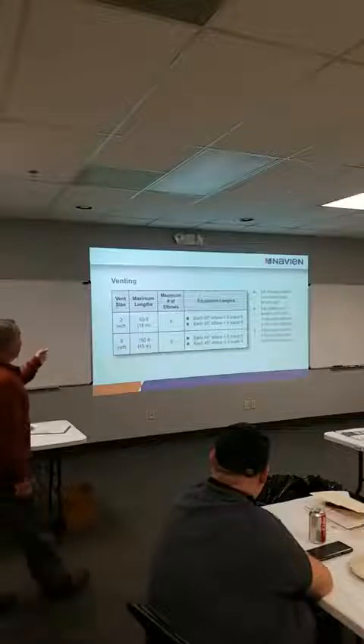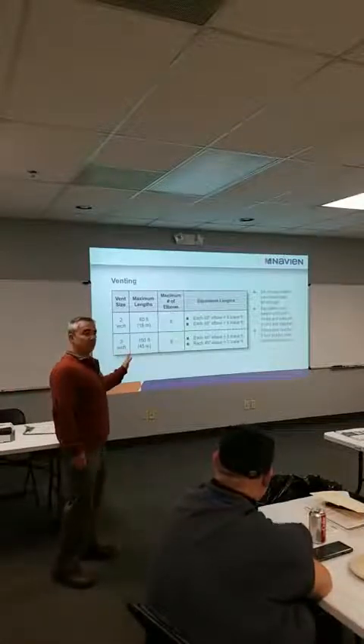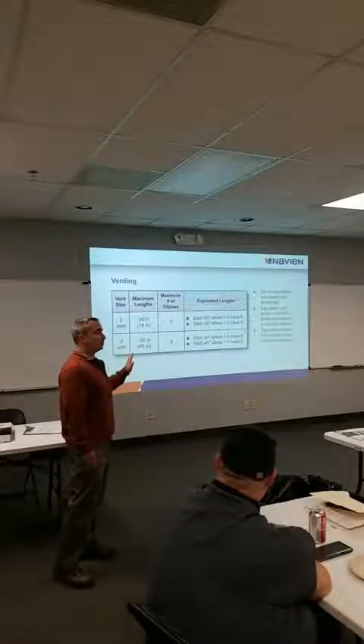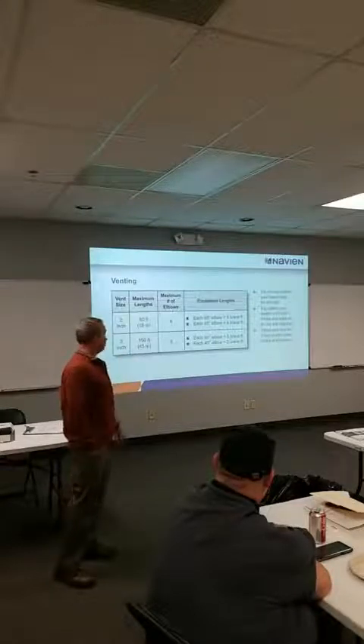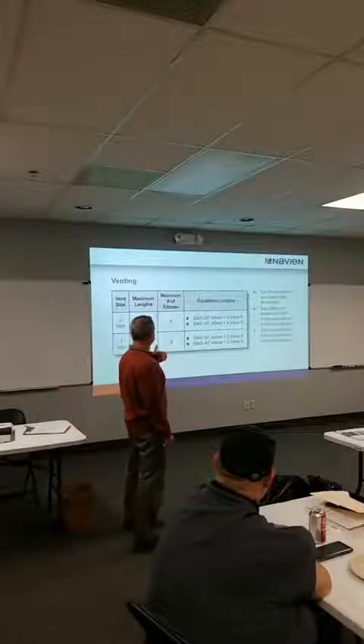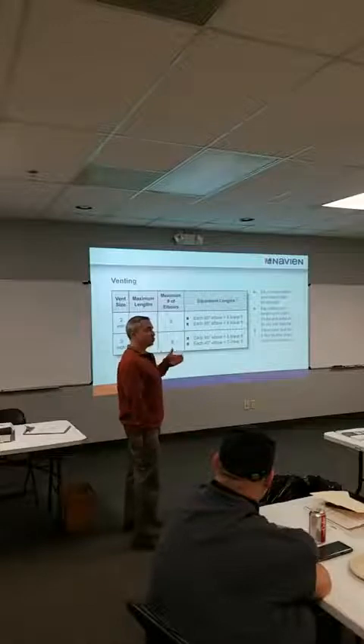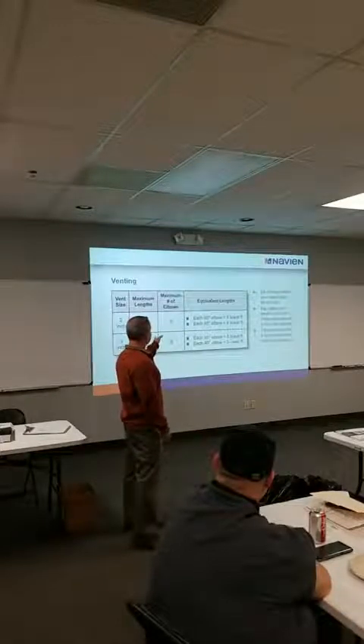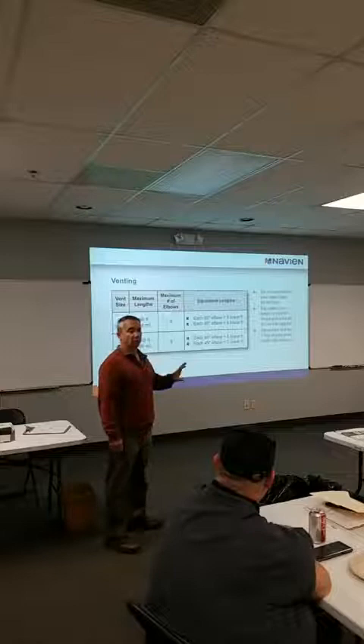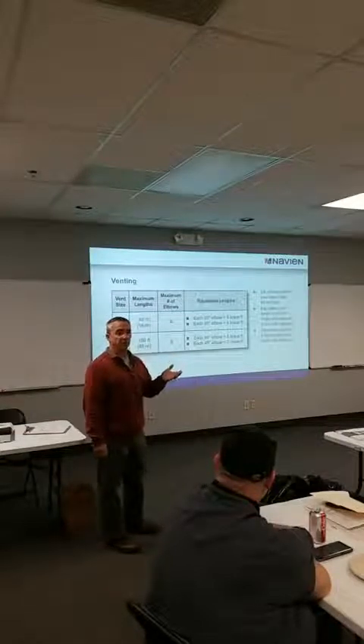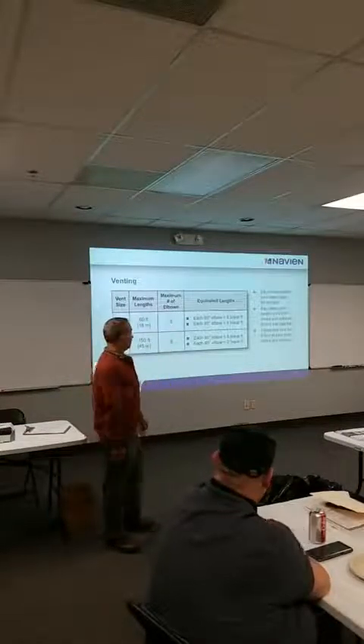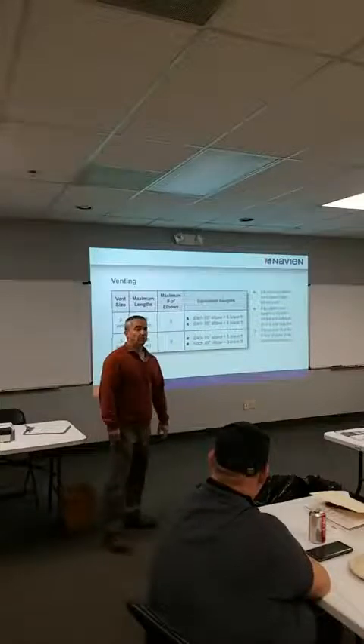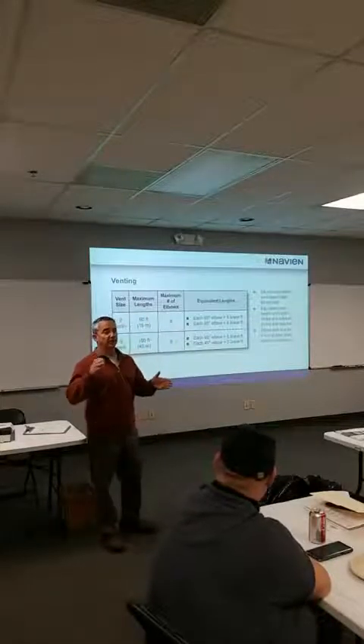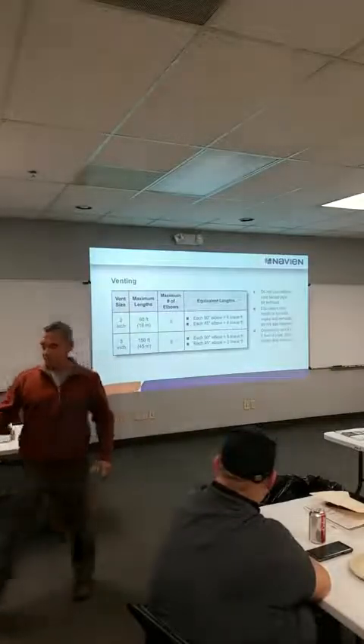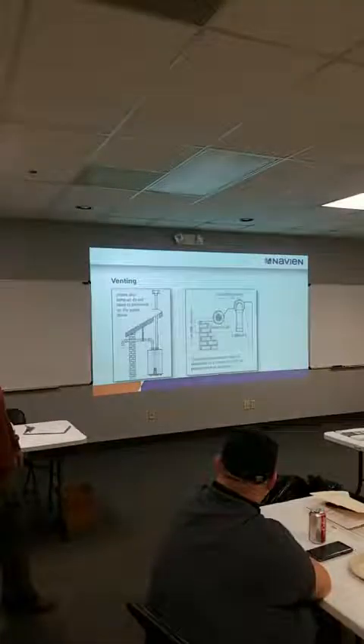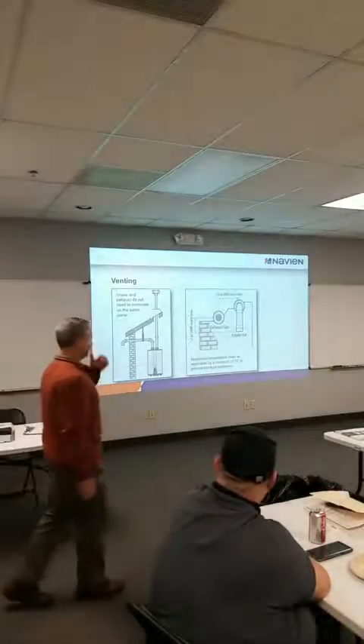Forgot to tell you, all of our venting on everything, again, with the commercial boiler, is identical. We don't change any of our venting rules at all. We're all 2-inch up to 60 feet, that's equivalent, max 6. So this little chart is good on everything but the commercial boiler. We basically go to 3-inch on the commercial boiler, and then we fall right in line. 60 feet is the distance on either line, intake or exhaust, not added together, and they can run anywhere they want. We don't care, as long as you don't run them underground.